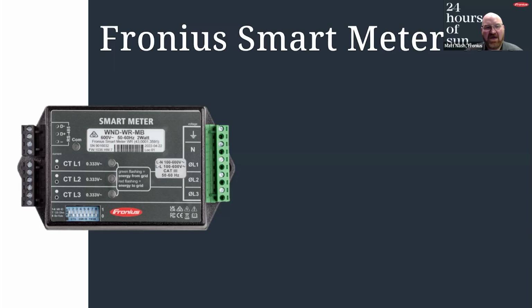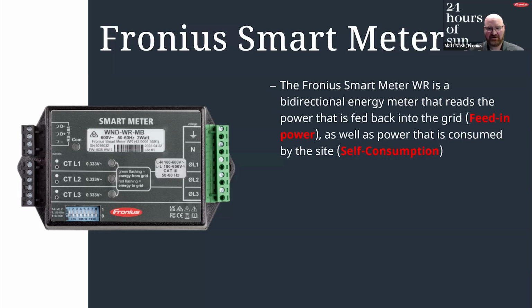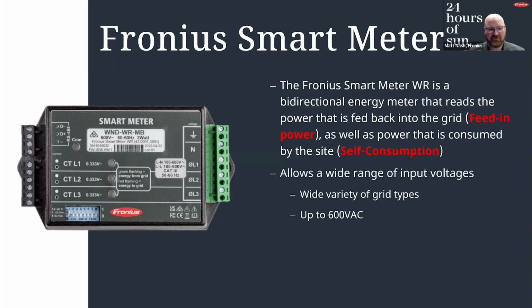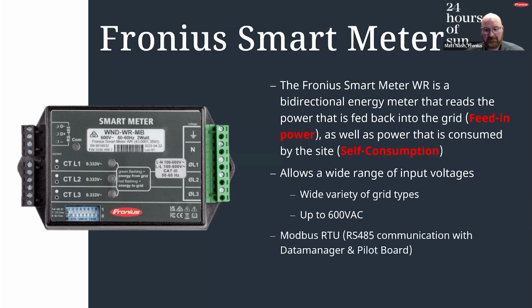All right. So we'll go ahead and talk about our Smart Meter Wide Range. This is our bidirectional energy meter that reads power that's being fed back to the grid, as well as consumption from the home. It offers a wide array of different grid types, up to 600 volts AC. And you don't have to worry about purchasing the wrong meter because it'll do anything from 208 to 600.